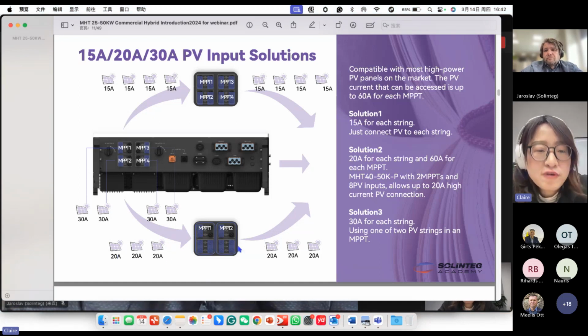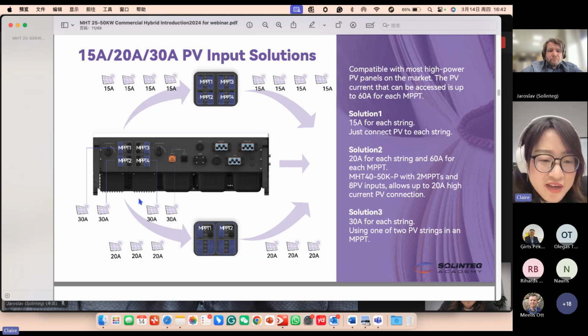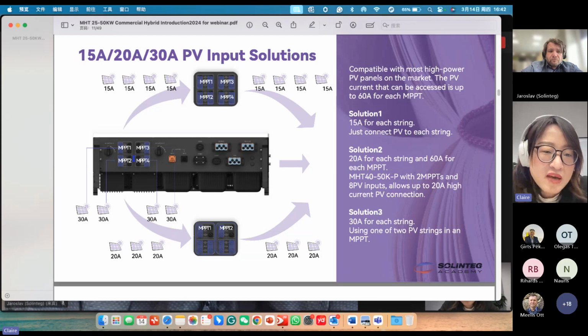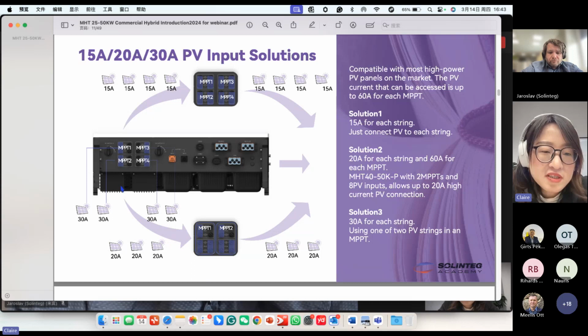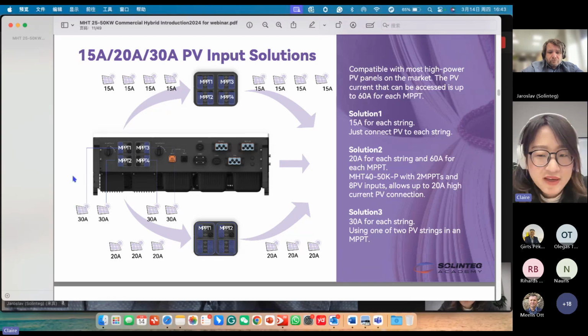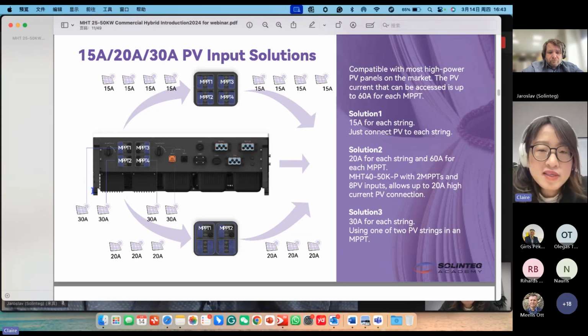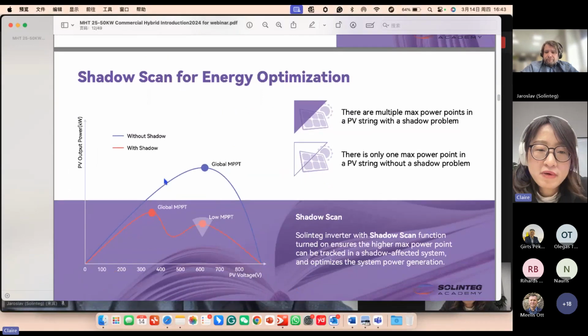Yeah, and in the future, if there are even higher current PV panels, we still have another solution. The customer can use the 4 MPPT version inverter and just use one PV string in one MPPT to connect PV panels with output current up to 30 amperes, like this. Yeah. So this is our tailored solution for the different PV panel connections. And we also support a very intelligent function like shadow scan.